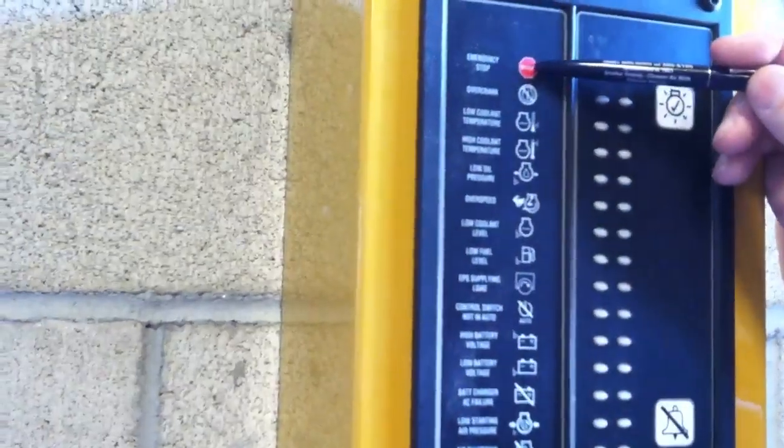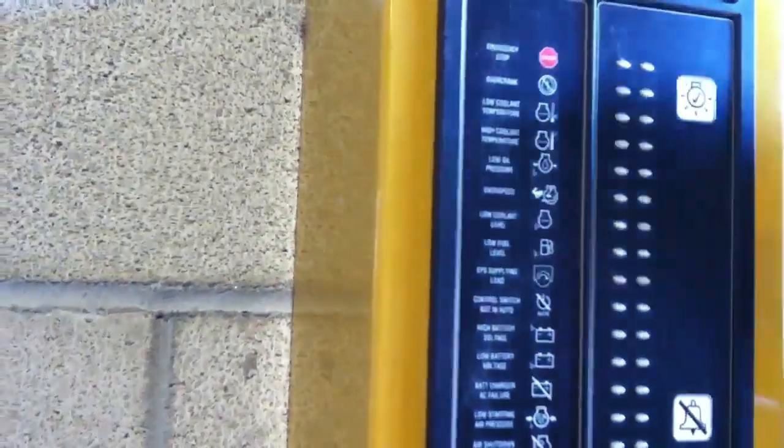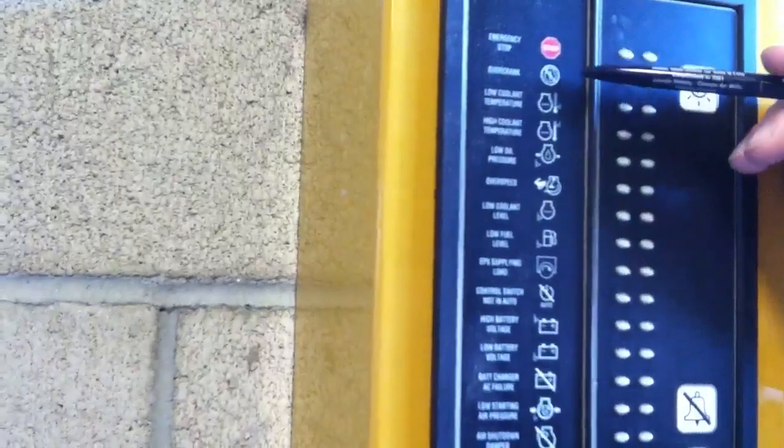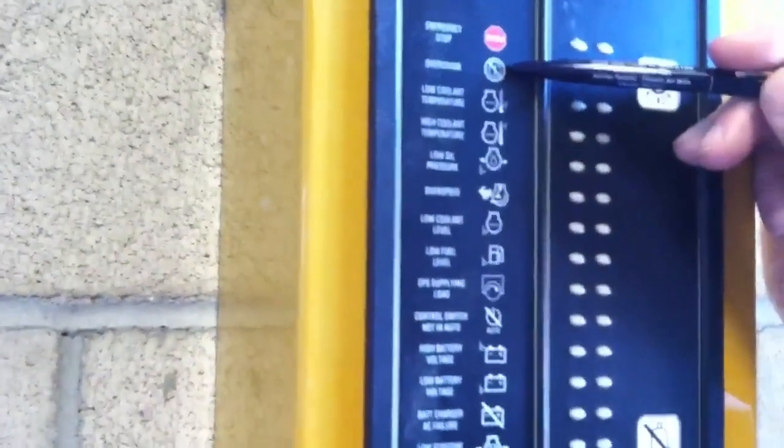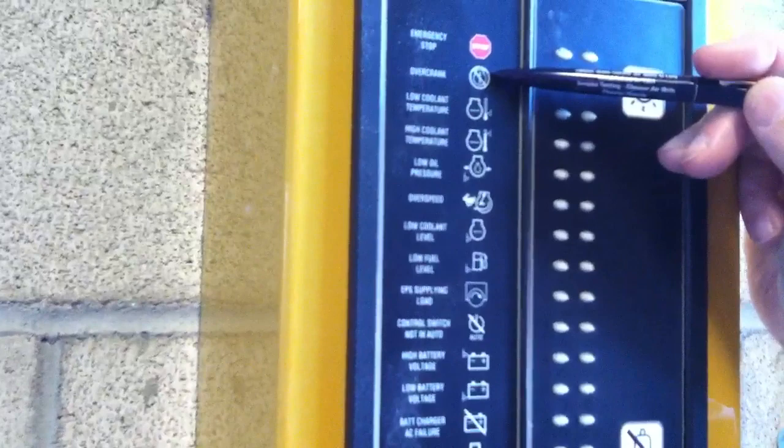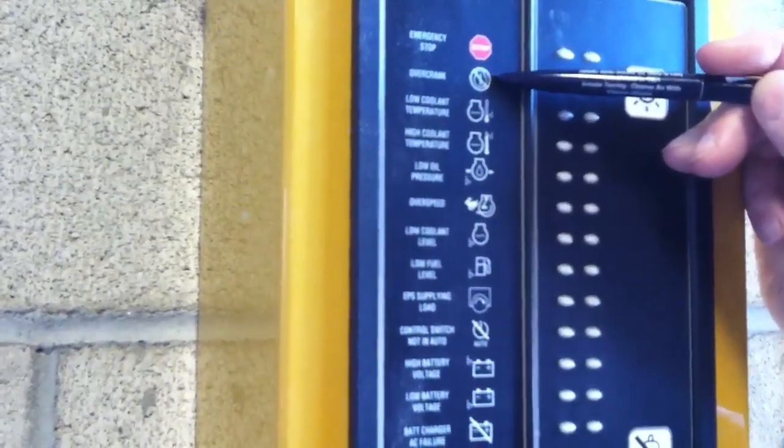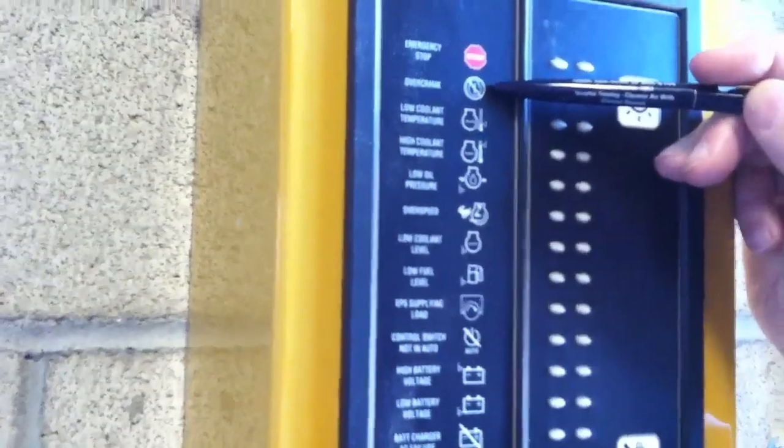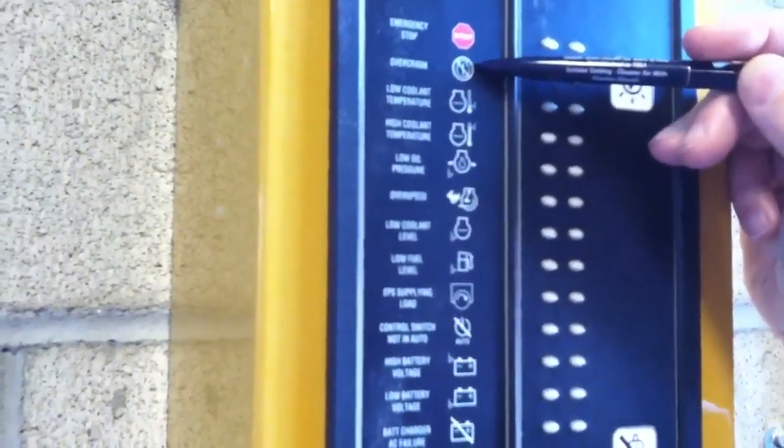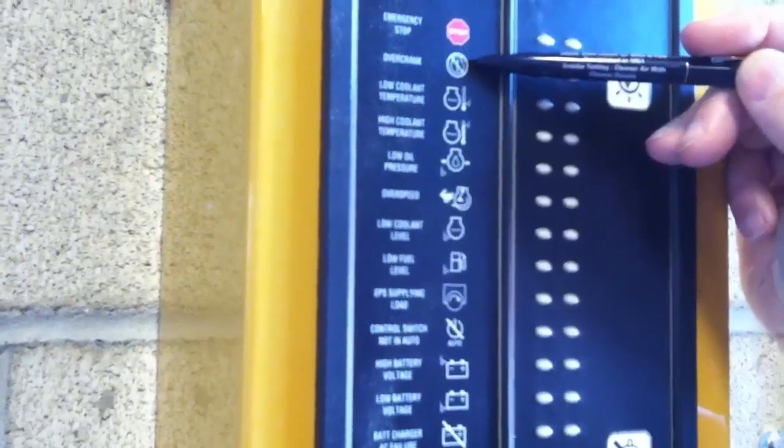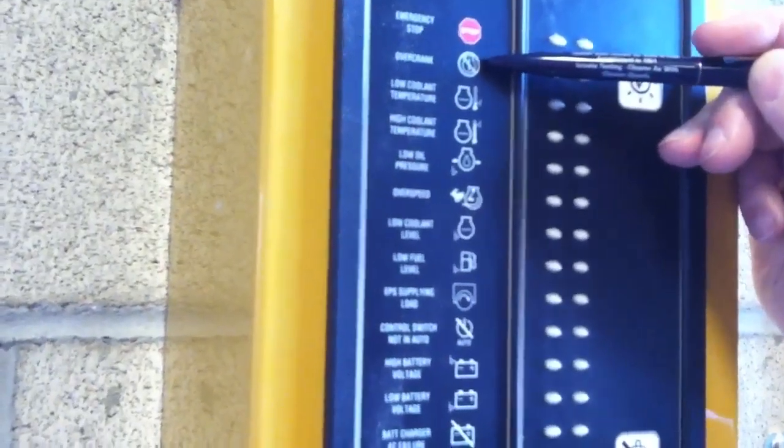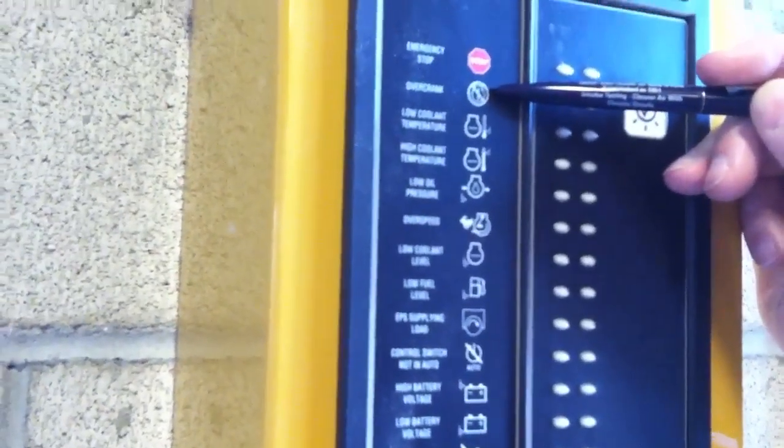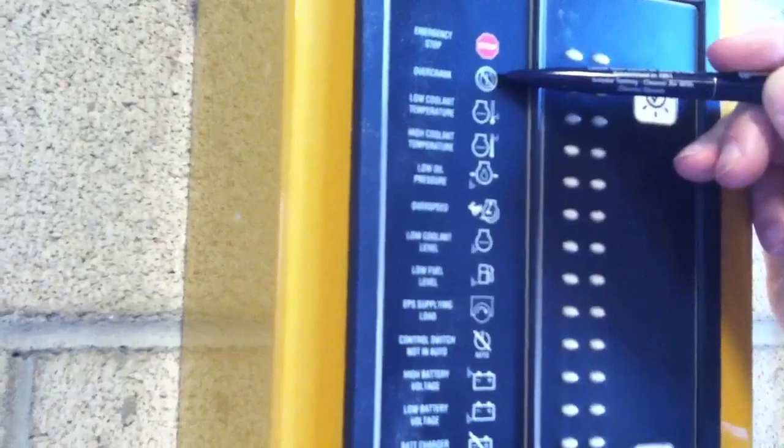That's emergency stop and again we did that at the engine. We have over crank which is a process where if we had low battery voltage or no fuel the engine would try cranking three crank cycles. And then it would go into what we call an over crank so it doesn't burn up the electrical system or the starter.